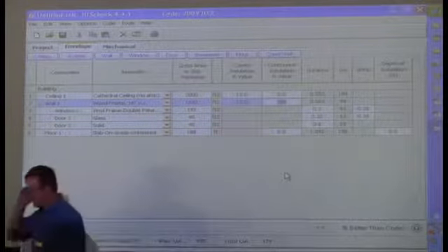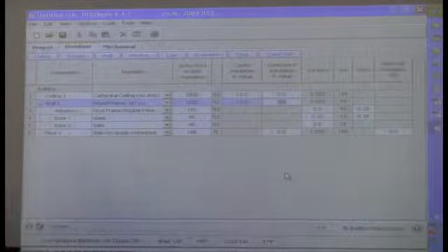And that's, in essence, how ResCheck works. So that's how you can show that you did a trade-off. And a lot of times, this is actually fairly easy to do because a lot of our windows are usually pretty good. Here I do 3.0, 0.3, and 0.3. I guess it's my solid door. I don't know. There we go. Need a better door. So you can play around with these, and here you can see we're able to successfully get the insulation along the roof line traded down to R19.